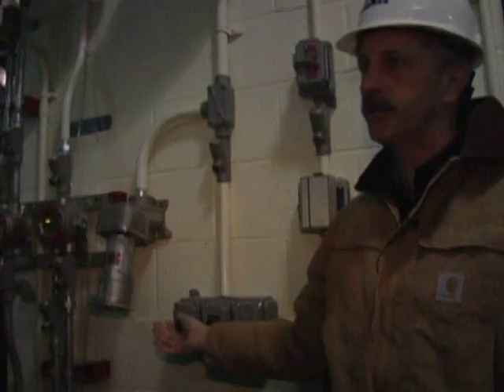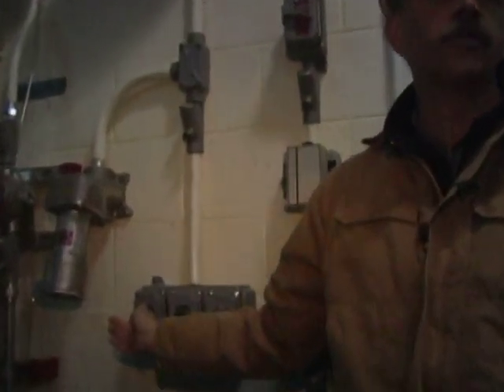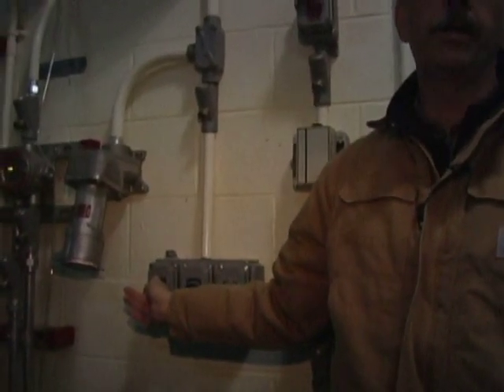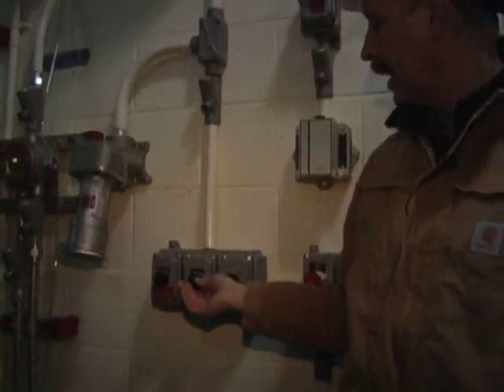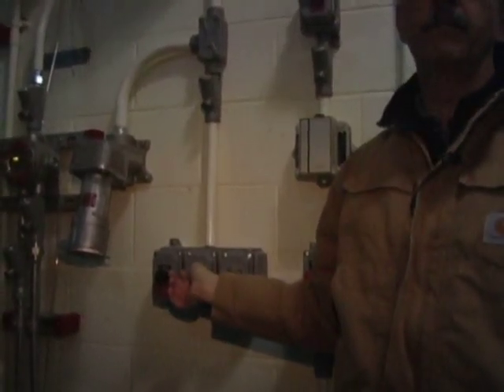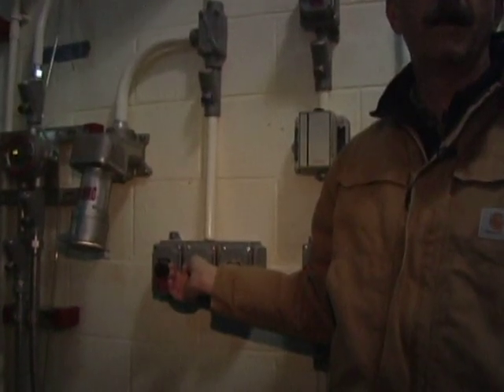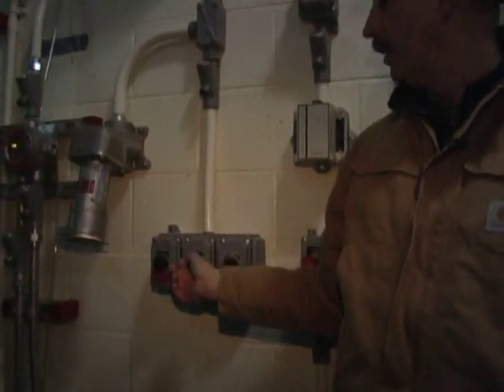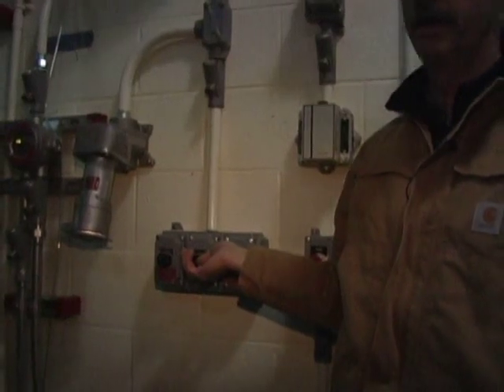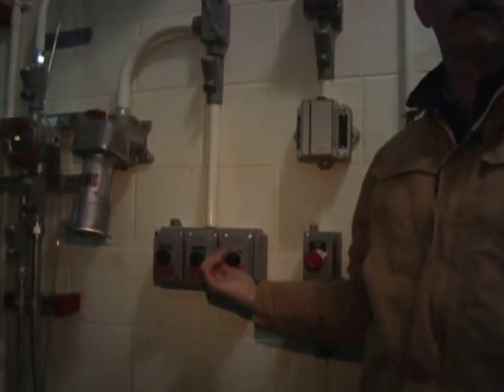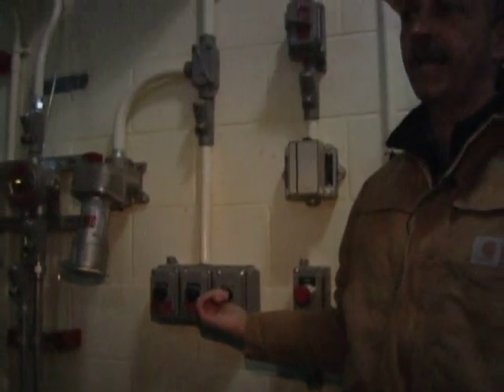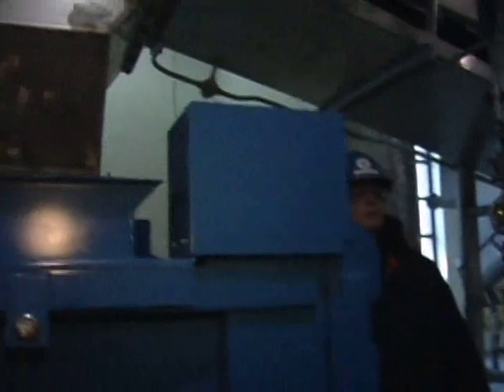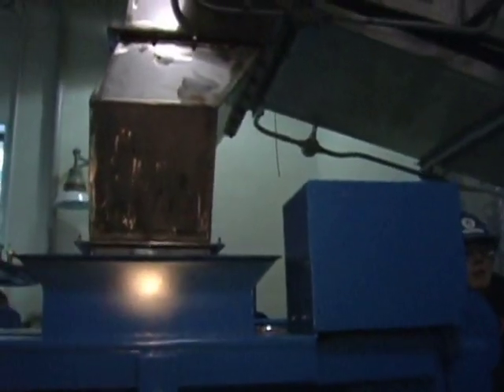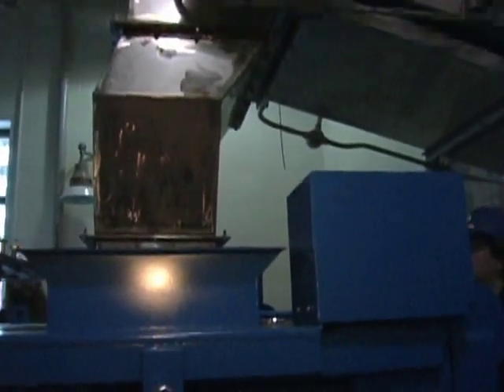You've got a hand-off-auto switch here, located locally, so you can run the equipment locally, or you can run it through SCADA. The labels on this have been misplaced. There are some additional labels that will be going on here, indicating that you've got a forward direction on the screw or a reverse direction. In this case, because it's an end-loaded container, the only reason I can see to run this in the reverse direction would be if you've jammed up and you want to free up that jam within the container itself to relieve some of the pressure on the screw. Other than that, this should be running in a forward direction all the time.